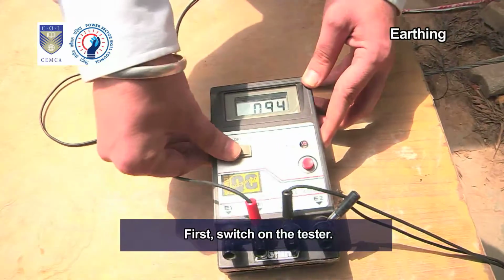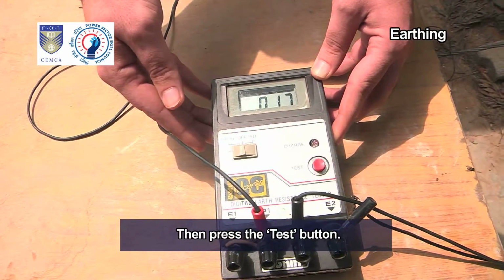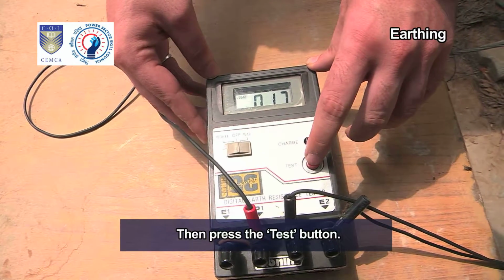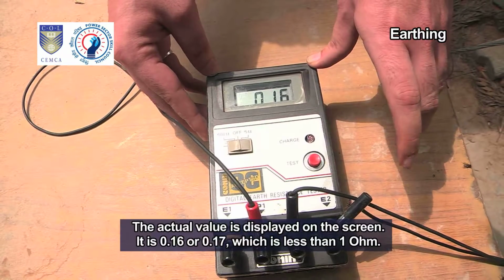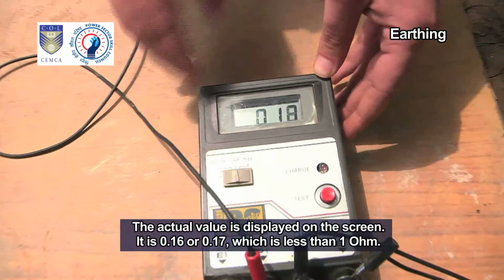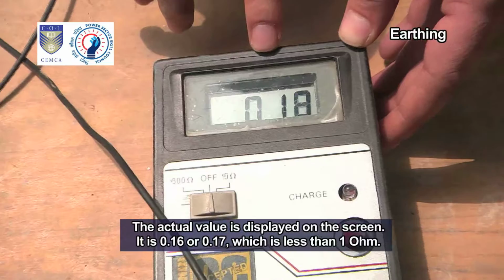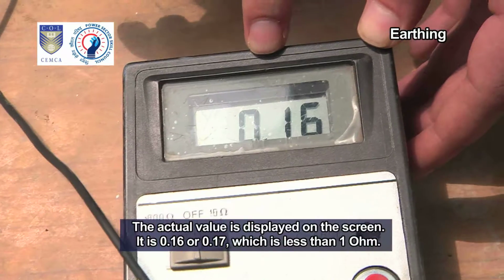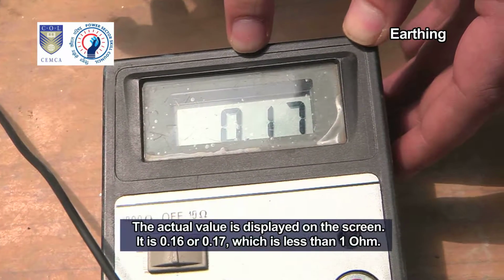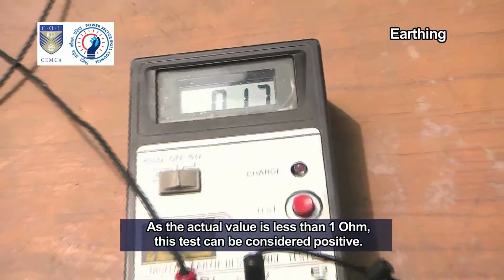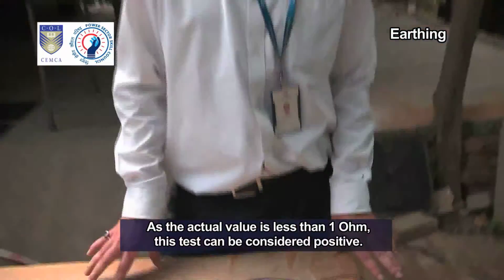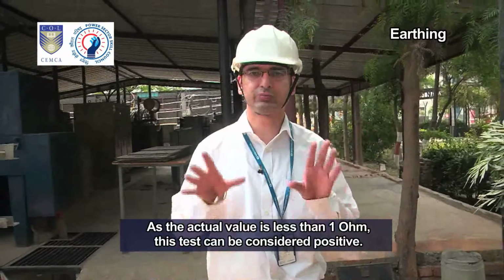Let us now see how to know the actual value using the digital earth resistance tester. First, switch on the tester. Then press the test button. The actual value is displayed on the screen. It is 0.16 or 0.17, which is less than 1 ohm. As the actual value is less than 1 ohm, this test can be considered positive.